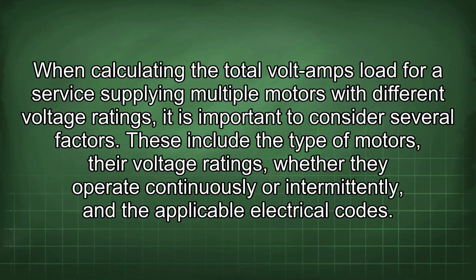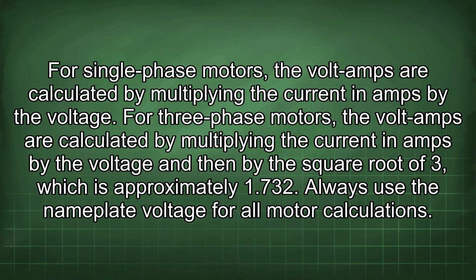When calculating the total volt amps load for a service supplying multiple motors with different voltage ratings, it is important to consider several factors. These include the type of motors, their voltage ratings, whether they operate continuously or intermittently, and the applicable electrical codes. For single-phase motors, the volt amps are calculated by multiplying the current in amps by the voltage. For three-phase motors, the volt amps are calculated by multiplying the current in amps by the voltage and then by the square root of 3, which is approximately 1.732.